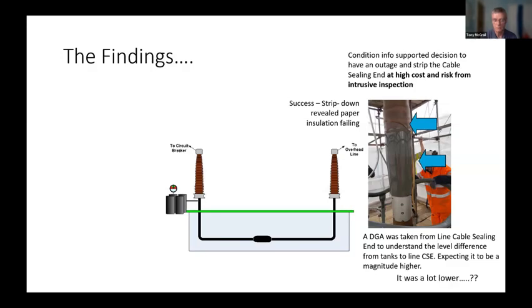And it was lower, way lower than on the other side. At which point you have to do some head scratching and say that this then is not the source of all of the DGA that we've seen in the expansion tanks. We've got a problem. We think we fixed it, but this is not necessarily the source. So we're going to go and have a look at the other end again, please.